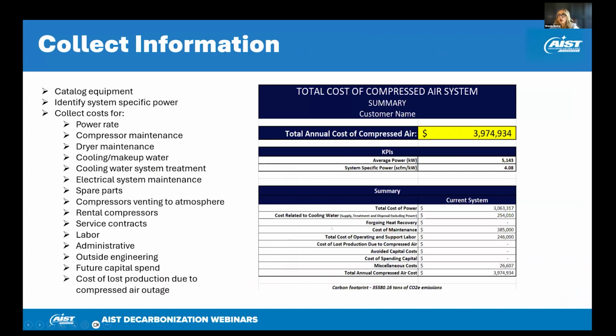And if you don't know where else to start, start by collecting the information. It's a good process to understand what's installed and how it's operating. A lot of customers do not have the data assessed to understand how much they're spending on their compressed air system and where they're spending their money. That will reveal opportunities in areas for improvement. So first, you want to catalog your equipment: look at all the nameplates in your mill, as far as compressors, flows, powers, dryers, and purge air. Identify what your mill is paying for power.